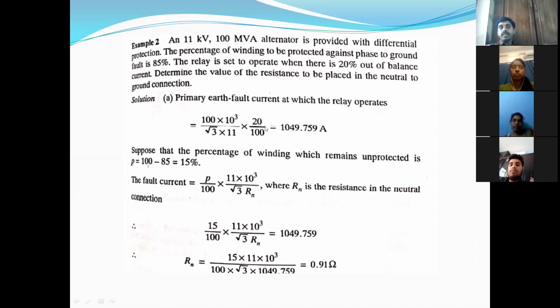For this case, the primary earth fault current at which the relay operates is based on 100 MVA, that means 100 MVA into 100 into 10 cube by root 3 into 11. What is this? The generated current. Of this, we have to take 20%, because they said 20% out of balance current. In the total current, we take 20%. That means 1049.759 amperes is the primary earth fault current. If the current is more than this value, the relay will operate.